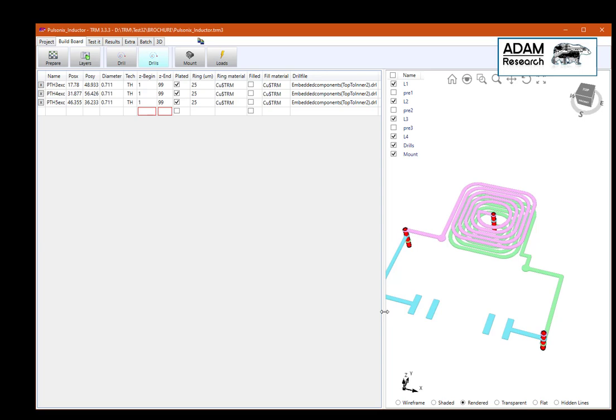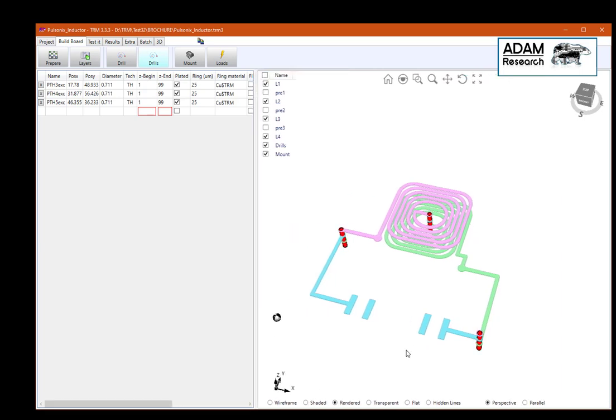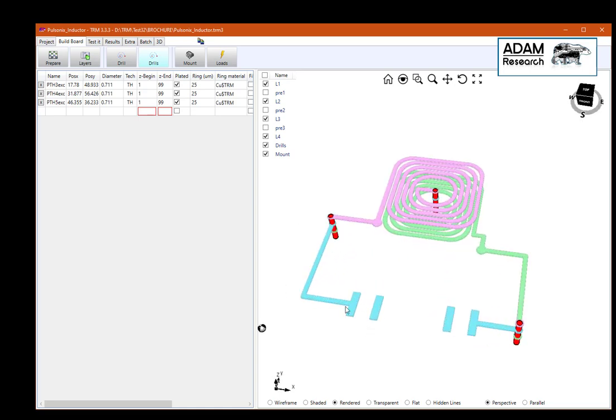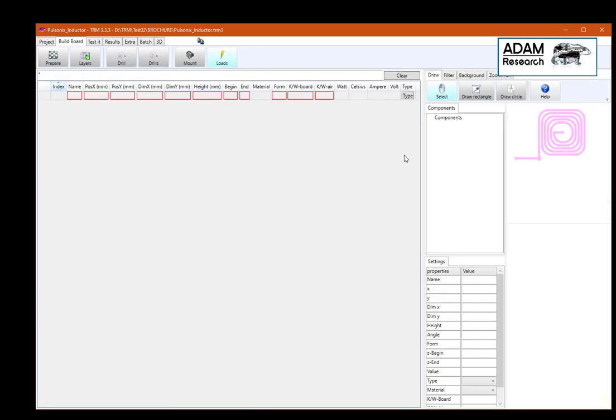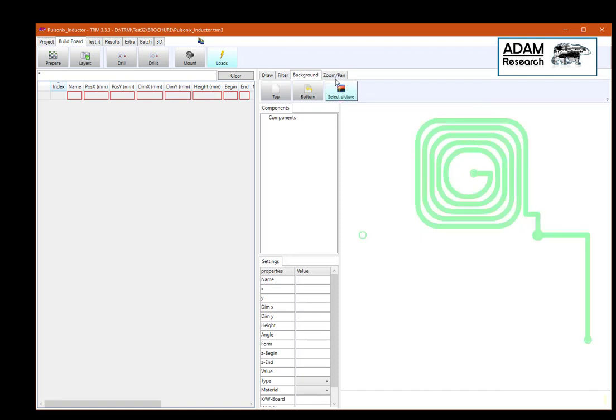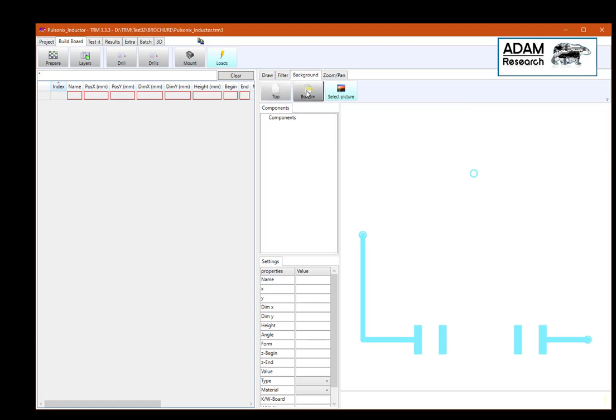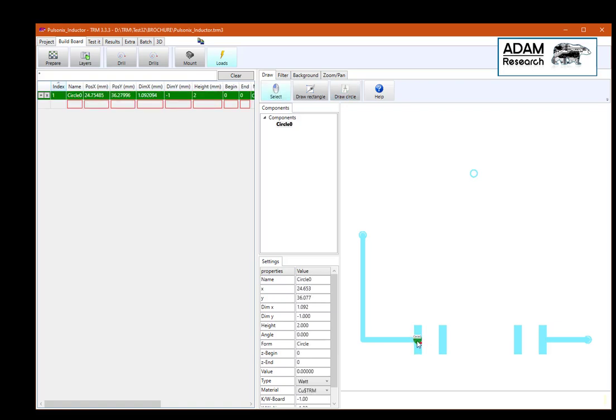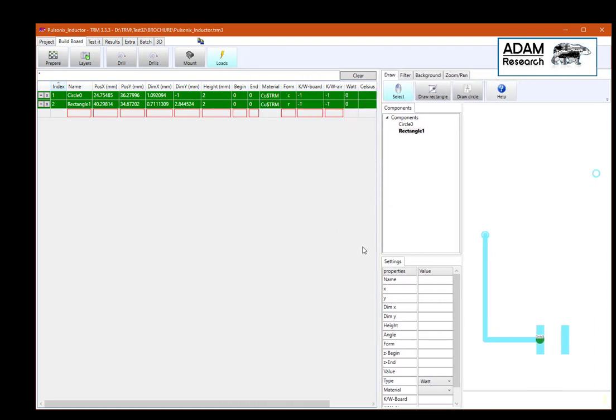Now we have to add some amp sources to bring in current, and this we have to do manually by drawing something here and something there using the graphic loads menu. For example, as a background image, I am using inner two, no, it should be inner one, and I draw just a circle here, and a rectangle there. And those two are now carriers of information. Circle maybe plus one amp as a test current.